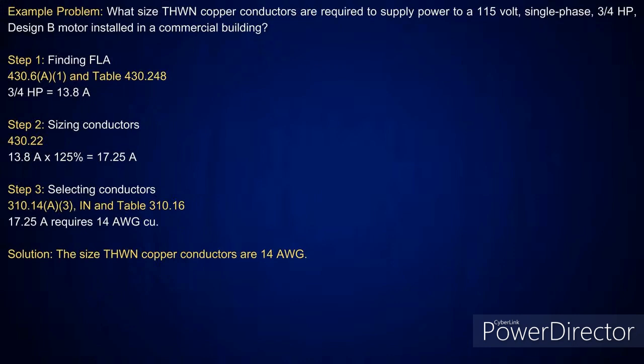Yep. When I look at 430.6A1, it says anytime, basically in a nutshell, this is what it's saying. Anytime I'm sizing my overcurrent devices and my conductors, I'll use one of the tables that's listed in tables 430.247 through 250. Okay? Right. So in this case, I'm going to size conductors here, and I have a 115 volt single phase, 3/4 HP, Design B motor. Okay? Well, since it's single phase, everybody should get used to this.